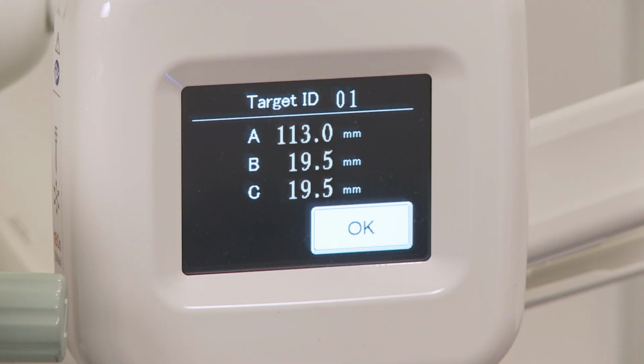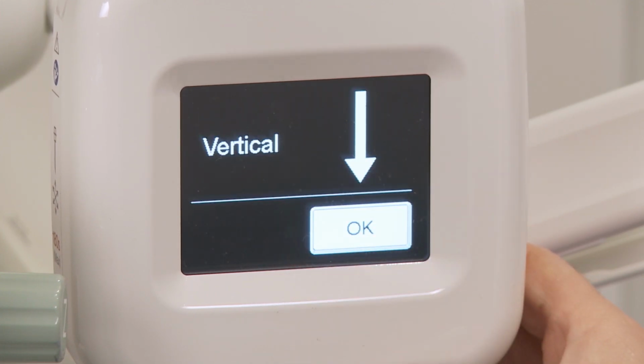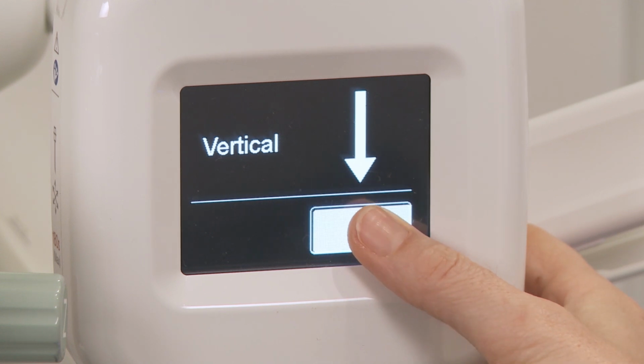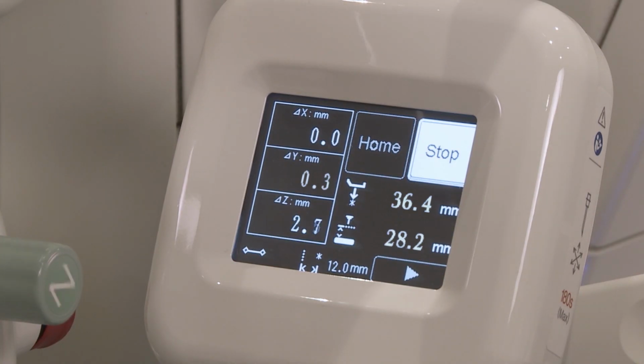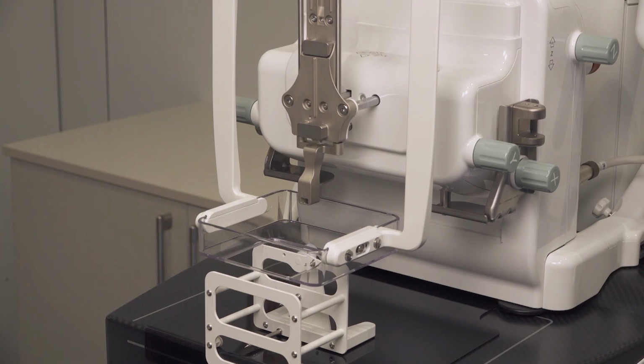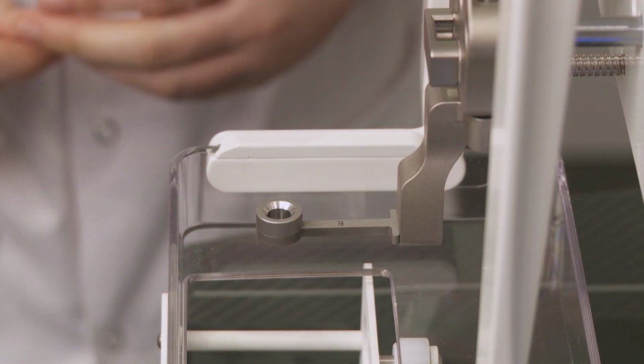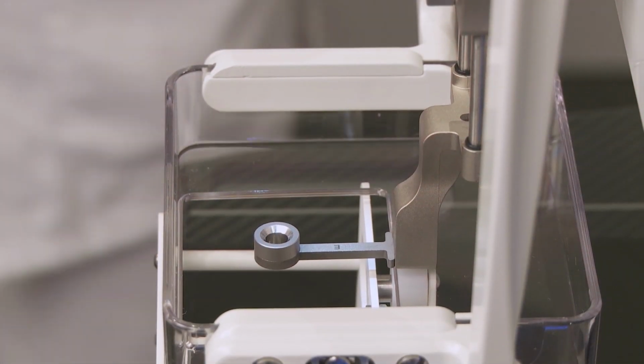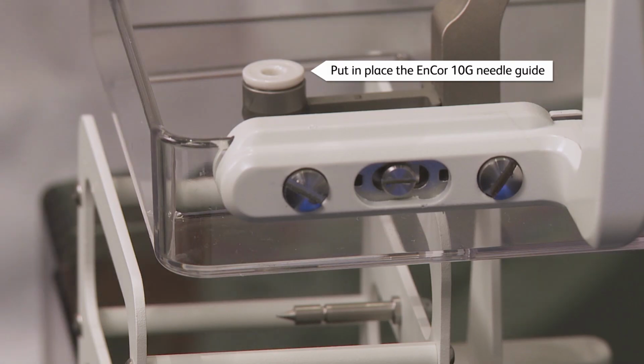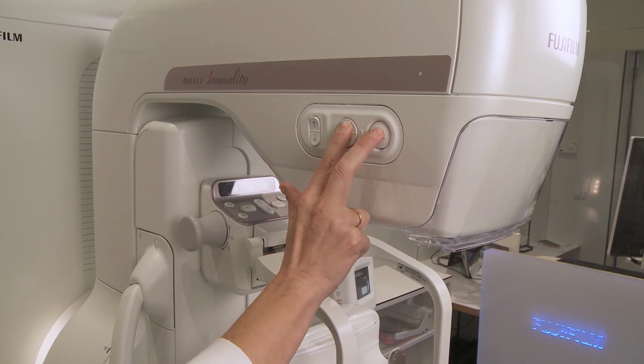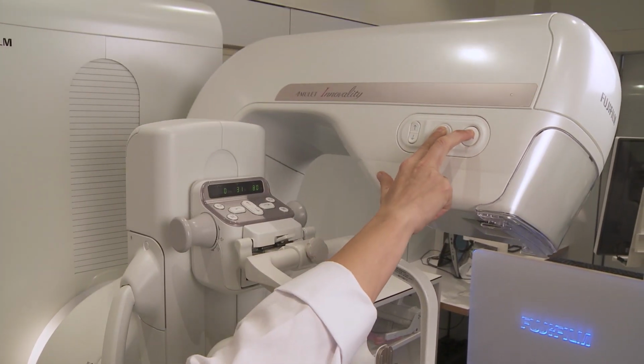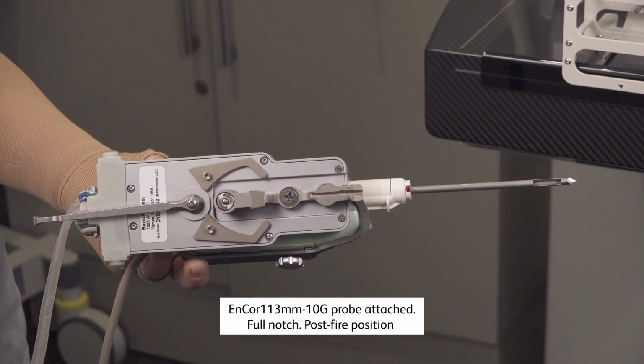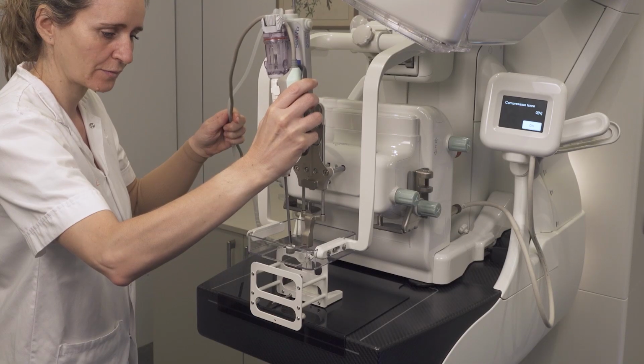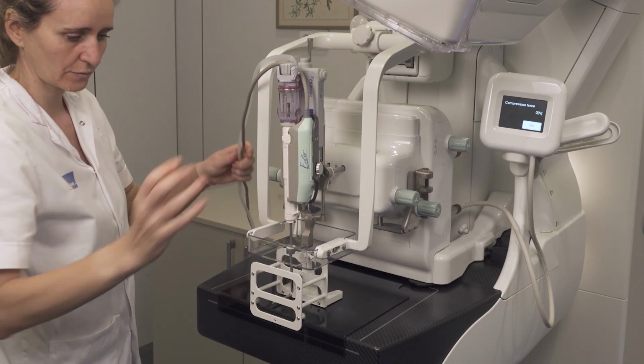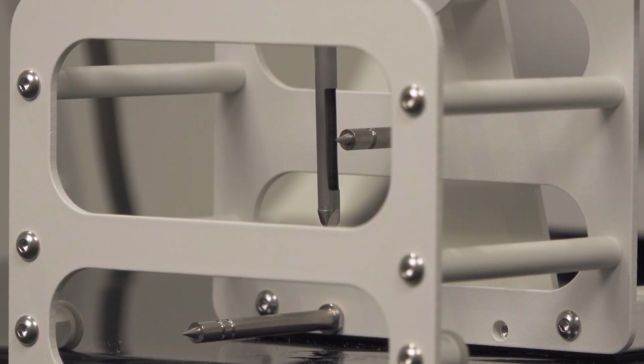In the Operation panel, the target information is displayed right after touching OK to confirm the target ID and needle, and OK again to confirm vertical approach. Press the Target button to drive the needle holder to the selected target coordinates. Attach the Fuji dedicated needle guide holder for EnCor. Lower the needle holder. Angulate the tube to free space for needle insertion. Insert the probe. The tip of the selected target should be about in the middle of the notch.